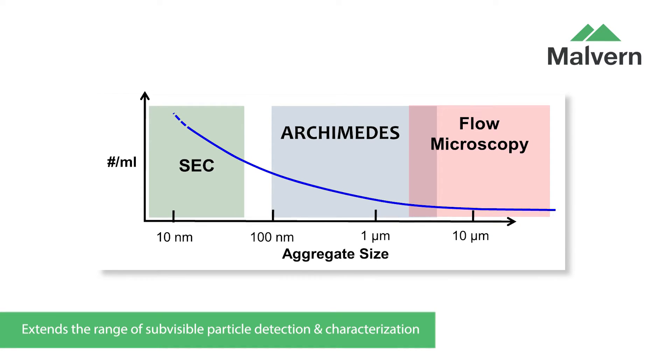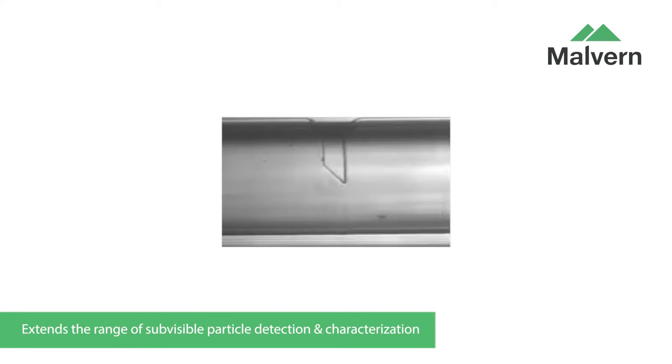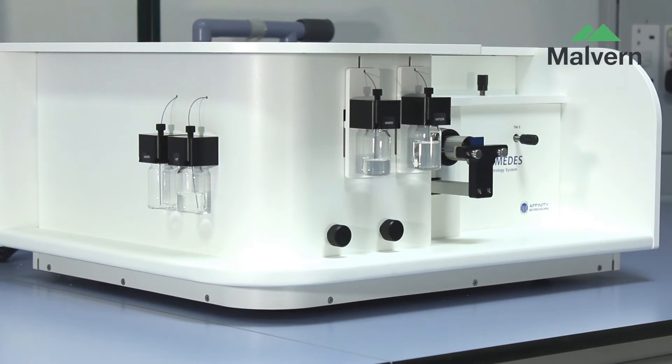Archimedes extends the range of quantitative and qualitative sub-visible particle measurement to include smaller sizes it's previously been difficult to analyze using other techniques. The technology it uses is called resonant mass measurement and it's able to give accurate and repeatable measurements of aggregate diameter, mass, and concentration.